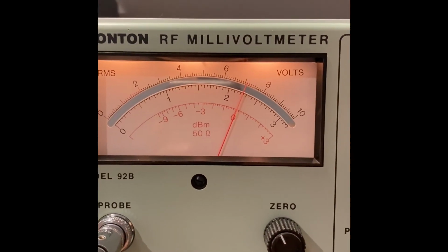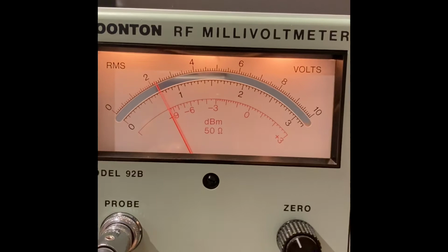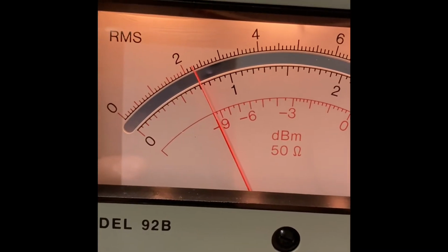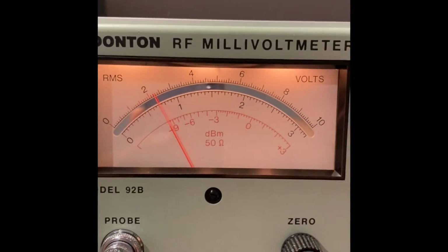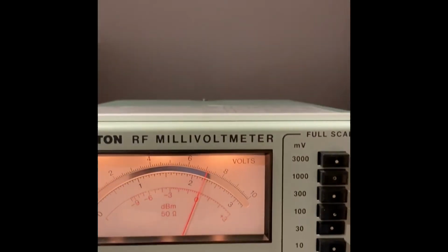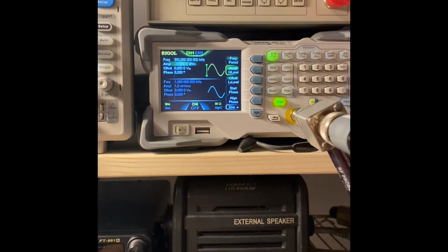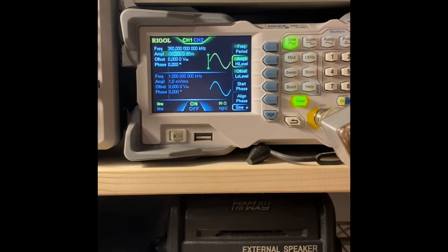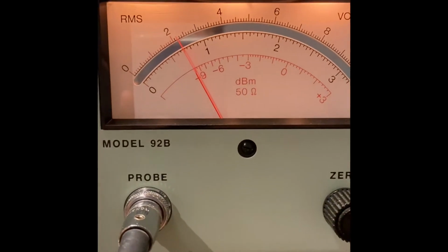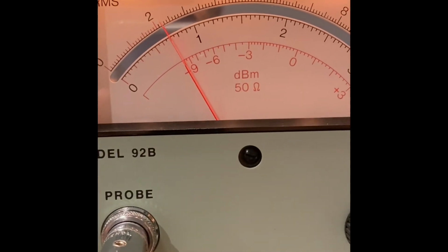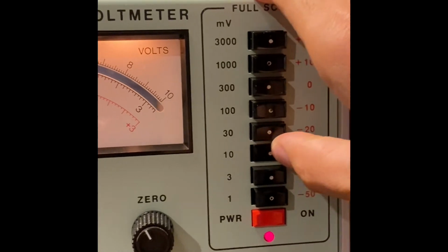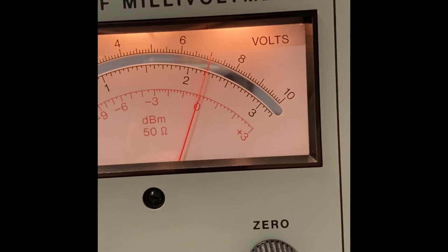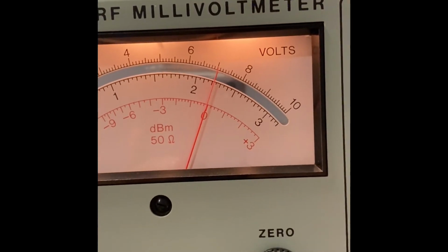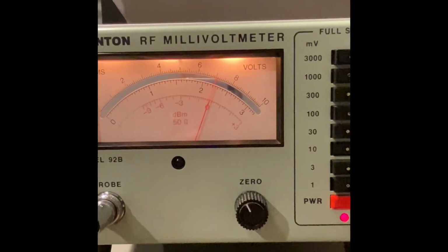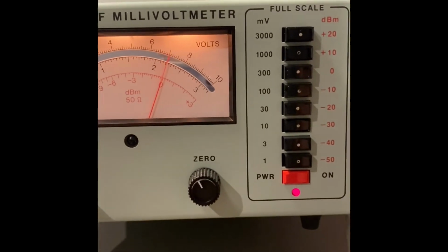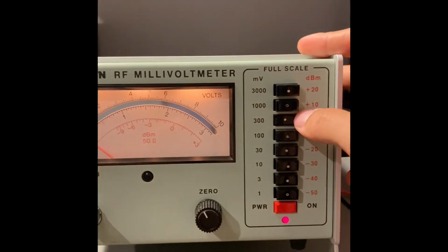If we change the scale now to the upward one, we should get over -10, which is the case. And if we now take, for example, 10 dB less, we go to -30, we see that we go over the -10, and switching scale, we should go to 0. And those are the fluctuations at the lower ranges. The issues I have with the instrument, but by the way, apart from that, it is calibrated. So let's have a look at 0 dBm now.